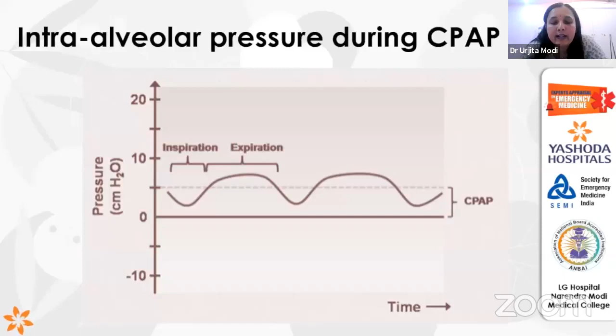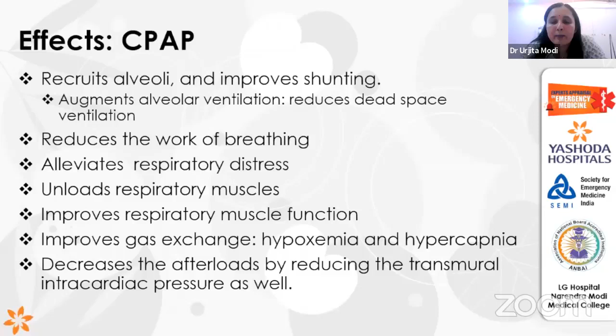Now, how does it work? As we know, whenever inspiration starts, there is a contraction of muscles. Because of this, the thoracic cavity volume is going to increase. At the same time, the pressure inside the pleura, the interpleural pressure, is going to drop below the atmospheric pressure. So whenever we need to use BiPAP, we need a machine which triggers, using either this increase in thoracic volume or decrease in pressure as an inspiratory trigger. So it is sensed by the machine, and depending on that, the machine provides inspiratory pressure or provides flow during expiration. We are going to discuss this in detail in the next slides.